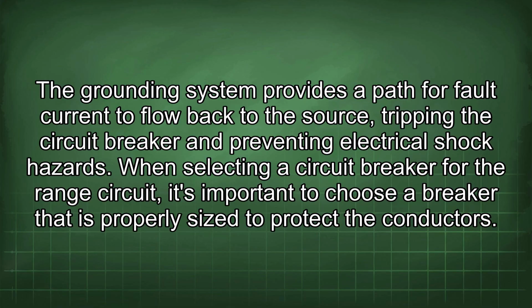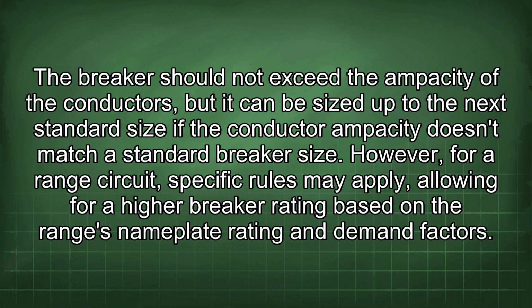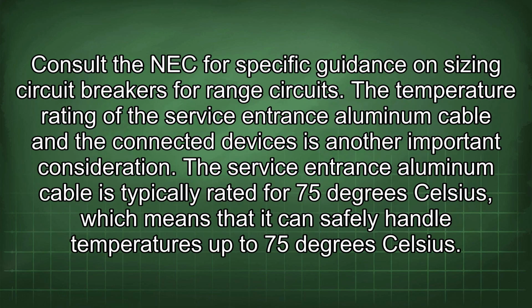When selecting a circuit breaker for the range circuit, it's important to choose a breaker that's properly sized to protect the conductors. The breaker should not exceed the ampacity of the conductors, but it can be sized up to the next standard size if the conductor ampacity doesn't match a standard breaker size. However, for a range circuit, specific rules may apply, allowing for a higher breaker rating based on the range's nameplate rating and demand factors. Consult the NEC for specific guidance on sizing circuit breakers for range circuits.